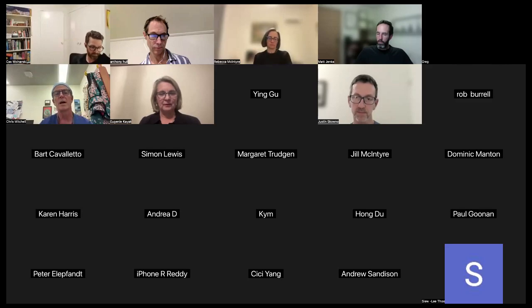So we've got multiple hospitals who have decommissioned, and I'm actually on the Australian standards at the moment, and we're writing in an extra section to the standards about decommissioning. But it'll probably take 1.5 years for that to be published. But the simple thing is that there's a really simple structure to how you should decommission your system. And probably in the next few months, I'll be able to do a quick blurb on how to do that. But the best thing is, and what the standard's going to say, is that you should cap off the wall first. And it's best if the cap itself has the words decommissioned or out of service on the cap, so a metal cap that screws in, that's used a wrench to tighten it up so that no one can just take it off with their fingers. And that's the start of the decommissioning process.